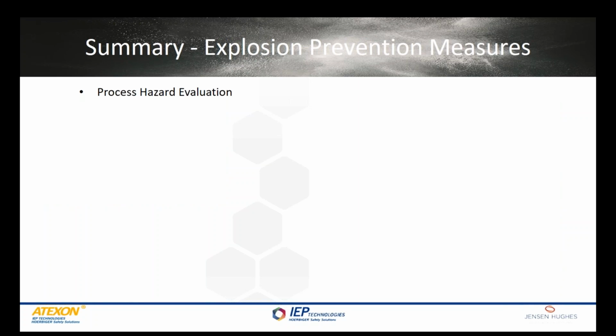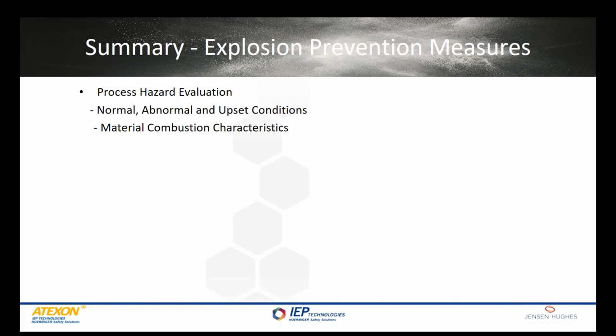We've covered quite a bit of material over the last hour, almost hour and a half now. Just as a brief summary of what we talked about: when you're trying to determine your explosion threats at a biomass facility, it's very important that you do a hazard evaluation that looks at what the normal conditions and the abnormal and upset conditions are that could occur within the facility. It also looks at the combustion characteristics, that is, is it possible to ignite the dust that's going to be found in the various vessels within the biomass facility under these upset or abnormal conditions.